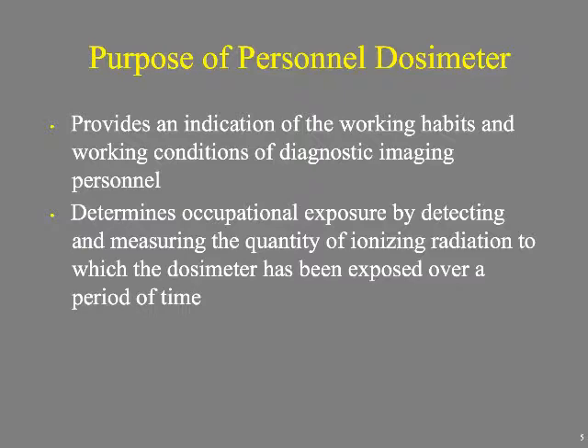The dosimeter also allows us to determine what types of radiation a person has been exposed to — superficial, eye level, or deep dose. OSLs are constructed with different filtration devices that let us determine: was the exposure sufficient only to irradiate the skin (like scatter), was it slightly more penetrating for the eyes, or was it primary beam deep dose?